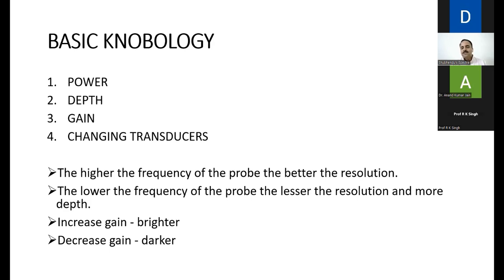So the higher the frequency of the probe, the better the resolution. The linear probe which we have has higher frequency, and hence we are able to get better resolution of the superficial structure. So better the resolution and lesser the depth. The lower the frequency of the probe, the lesser the resolution and more the depth, like the curvilinear probe. The curvilinear probe gives us good depth analysis, but with a lesser resolution.